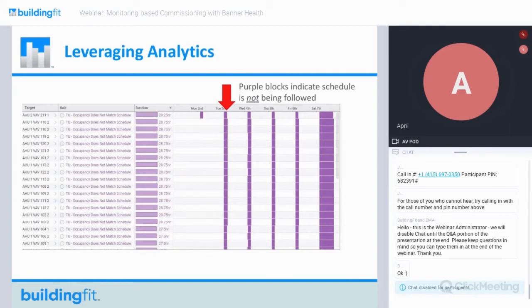By monitoring high-level KPIs like the building energy use, fan power, and reheat load, we noticed drift occurring. One of the contributing issues we identified was this: the terminal unit scheduling slowly started to get rolled back, and the occupancy schedule no longer matched the original design intention of the overall project.